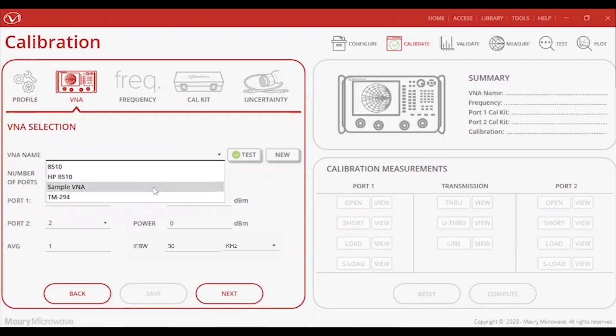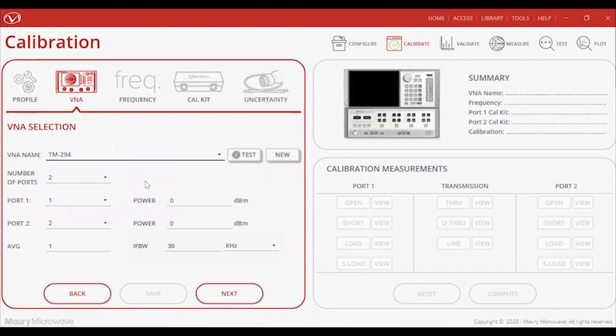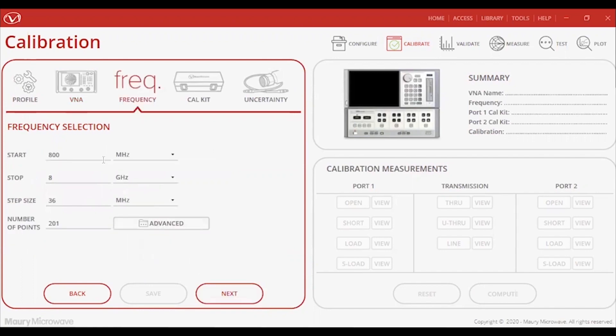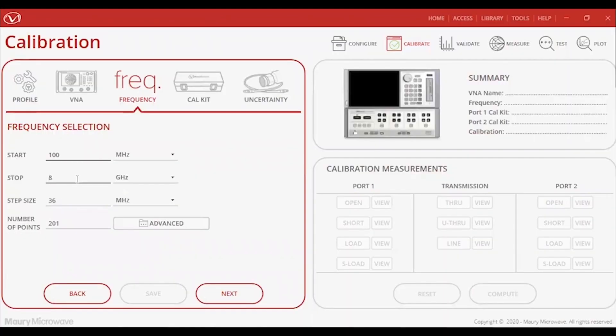After completing the profile setup, I'll move on to the VNA selection tab. Here, I'll go ahead and choose the 8510 previously configured in the last module. You can then designate the ports wanting to be used, as well as set the averaging, port power levels, and IF bandwidth. I'll then set the frequency settings such as start and stop points, step size, and number of points all in one interface unlike the front panel process of the 8510.